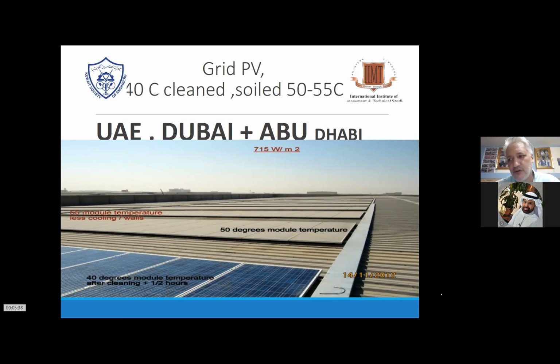That's a fact. Some inverters or some modules are too high in current, so they can only do like 15 amps. That's the old version of the modules. Now you have inverters or modules with 10 amps per string, so you cannot double up the 10 amps per string because you're exceeding what the inverter can take, which is 15 amps. So you have to think 5 years back and 5 years ahead, and with every different technology, as we saw when we went from 600 volt to 1000 volt, and now from 1000 volt to 1500 volt, it's evolving and changing, and the modules change too.